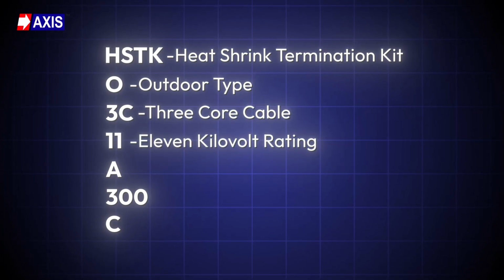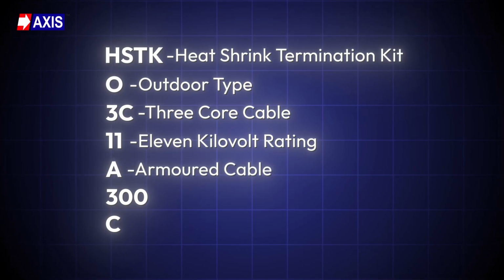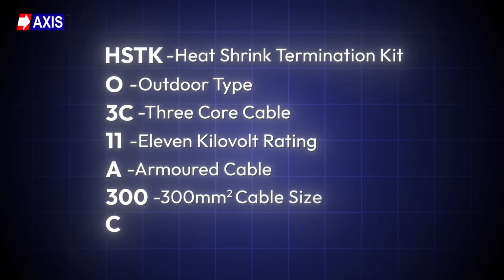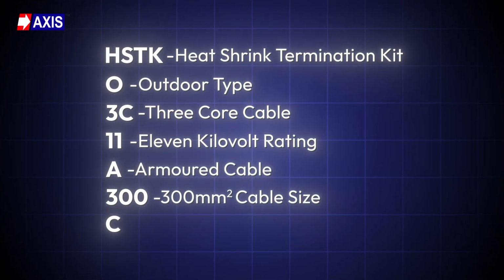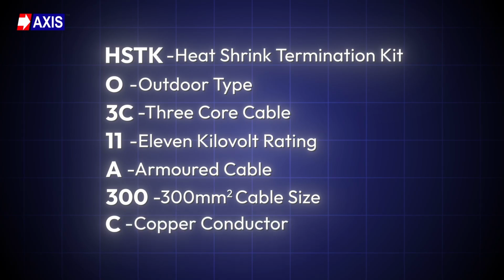11 means 11 kV rating. A indicates armored cable. 300 refers to 300 square millimeters cable size, and C stands for copper conductor. So just by reading this simple product code, you can match it with your exact cable details. You might notice that some factors discussed are not part of this code. That is because not every requirement can fit into this format. In many cases, we customize the termination kit based on your exact application and installation conditions.